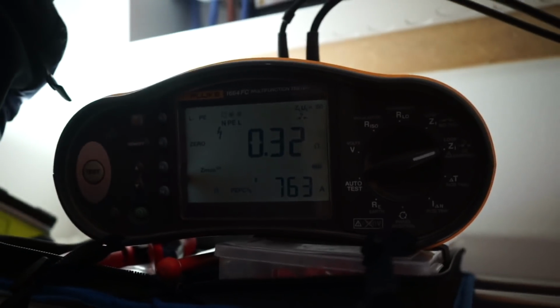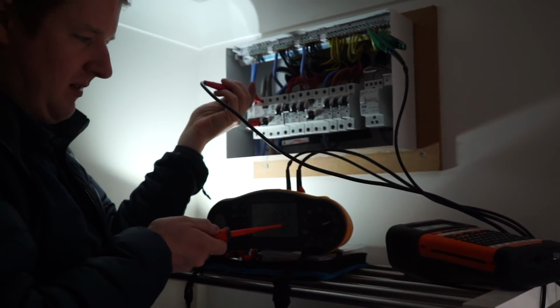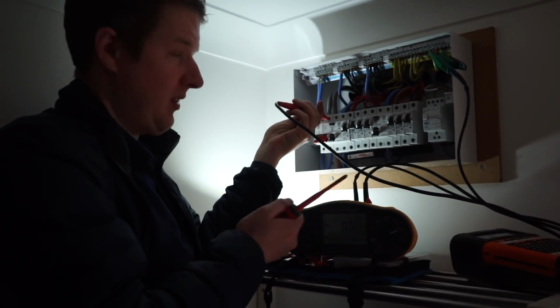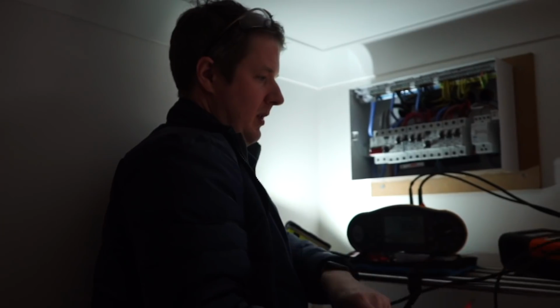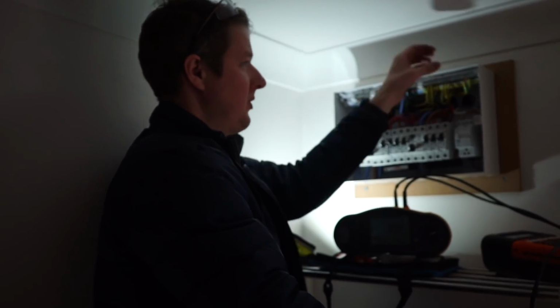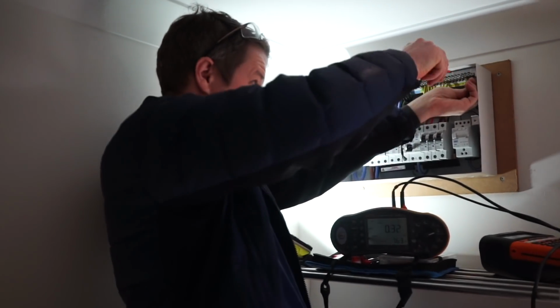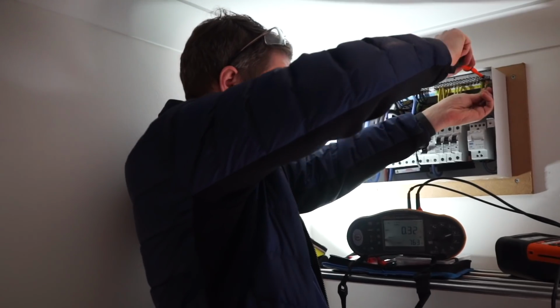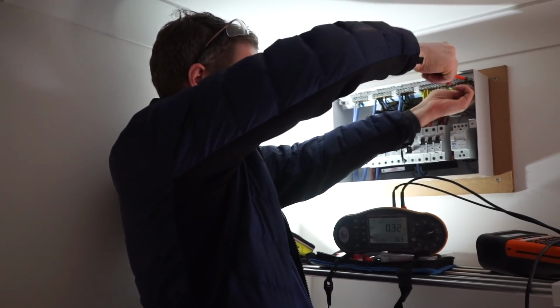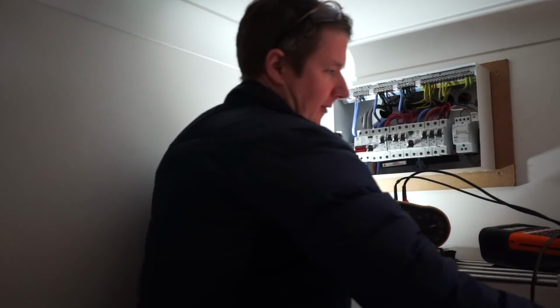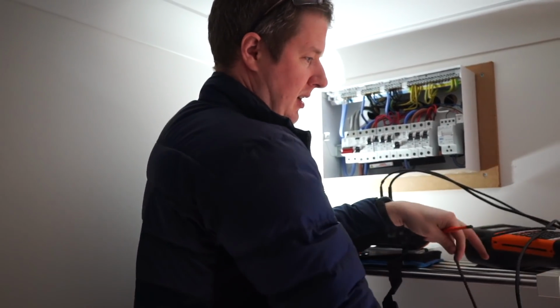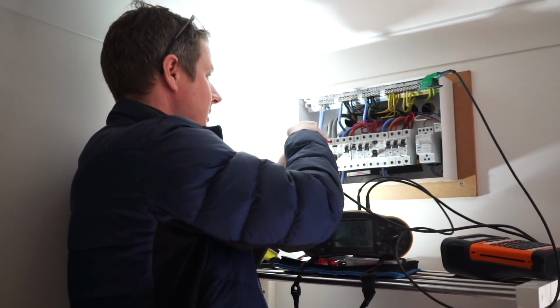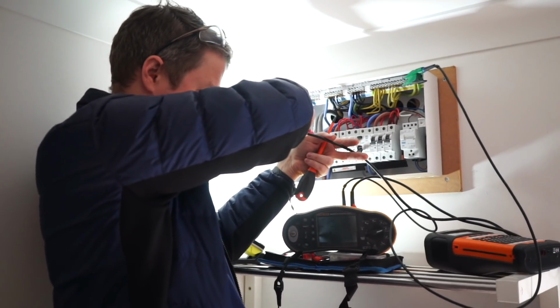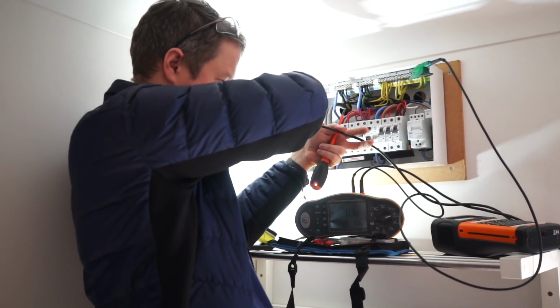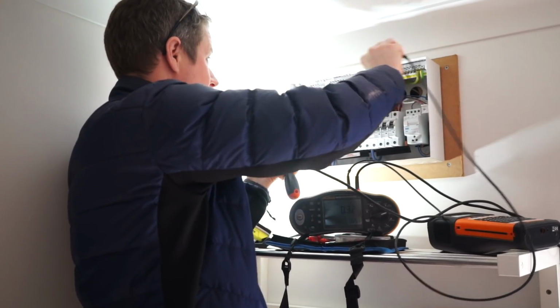0.32, which is fine. I believe it's a TN-C-S system, so the maximum acceptable reading is 0.35, so we're within that, which is good. And then what I'll do is reconnect that, and then just do another test with it reconnected, just to see what the reading is and to check the prospective fault current on the installation. We're just doing minor works, so you don't even record half of these readings on there, but I like to check anyway, just to make sure.